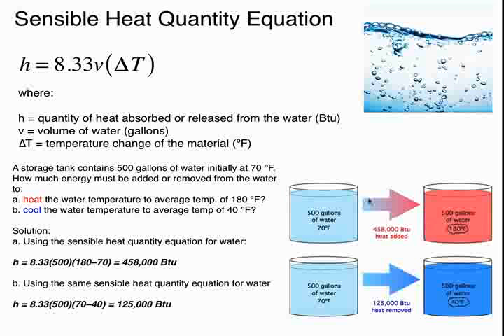And again, a little bit of simplification here. We're saying this tank is completely uniform at 70 degrees, as well as this tank here. So we just plug the numbers into the formula. We have 500 gallons of water. It changed from 70 to 180. So you can see that's almost 500,000 BTUs of storage. Now, think about that in the context of a house where you might have a design heating load of perhaps 30,000, 35,000 BTUs per hour. That's several hours worth of heat in that tank of water.